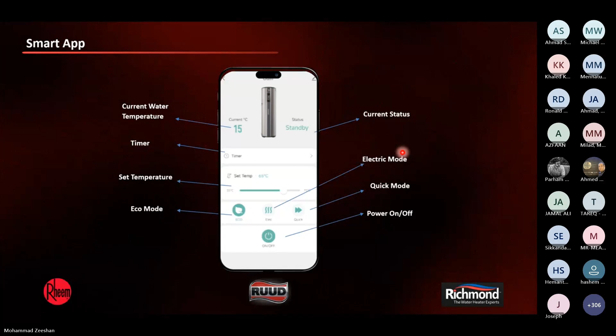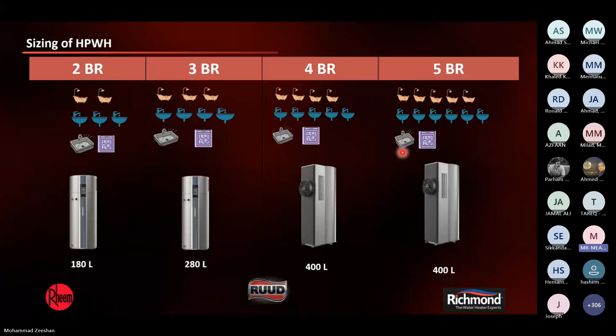In terms of sizing these heat pump water heaters for 2-bedroom, 3-bedroom, 4-bedroom, and 5-bedroom villas, you have different capacities to choose from. For a 2-bedroom, go with the 180-liter capacity. For a 3-bedroom, about 280 liters. For a 4 and 5-bedroom, you can use multiples of the 280 liters, or go with the bigger 400-liter units. That flexibility is provided by us.